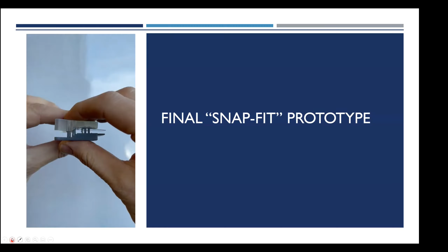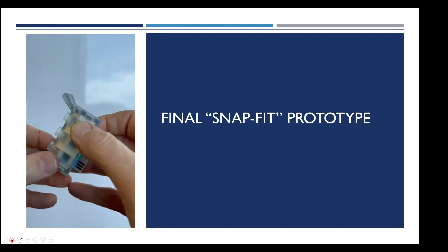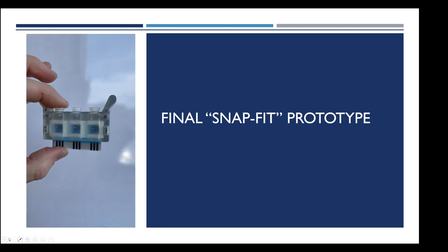And now the two halves are snapped together and we are not able to pull this apart. So I tried here to pull it apart and you'll see that I can't get it apart. So that's what we want. We wanted the thing to stick together and not come apart once it's snapped together. And there you can see the little electrode and the adhesive gasket. So now that little cartridge is ready to use, we just have to put a cap on the top and then it gets injected with the samples and the electrodes will read the samples in that detector, which is really cool.